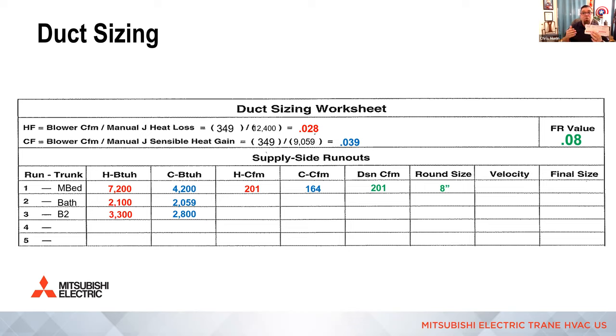Now, a question always becomes, do we use 7 or do we use 8? And that's where velocity comes in. So velocity will tell you, do you use 7 or do you use 8? You don't always go bigger because sometimes the air now is going to move so slow, it barely blows into the room and it doesn't hit your design. It doesn't mix the room and we have hot and cold spots within that space.